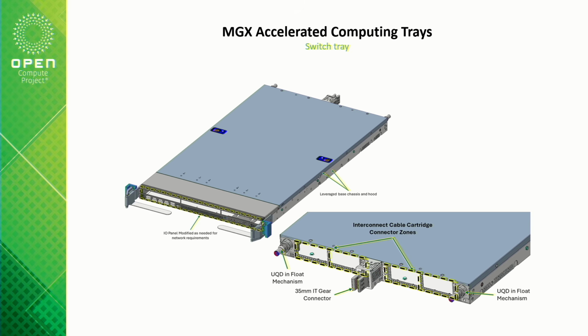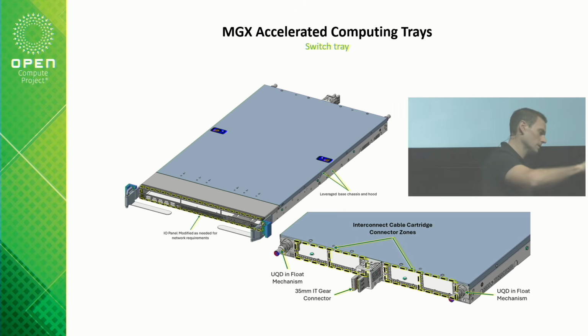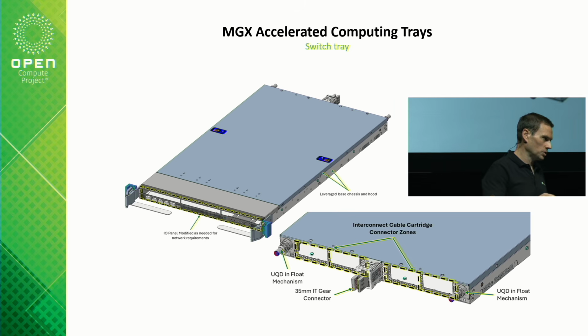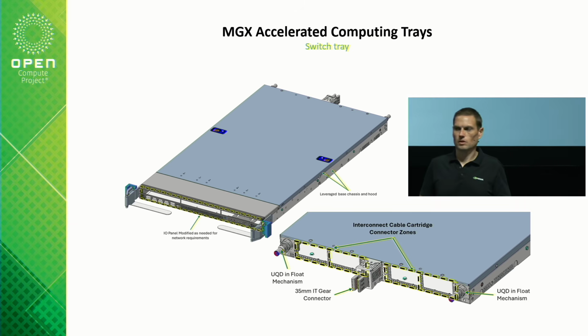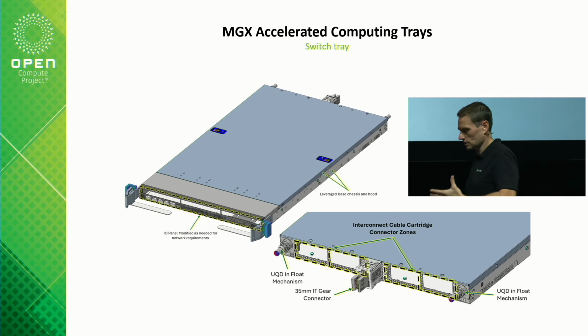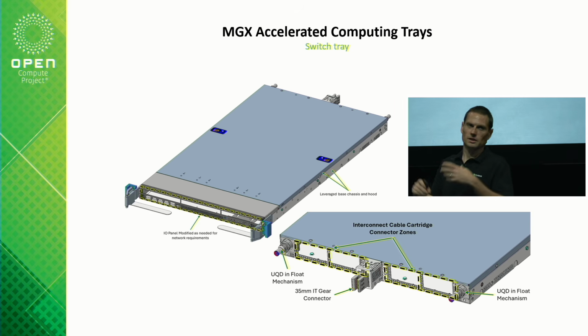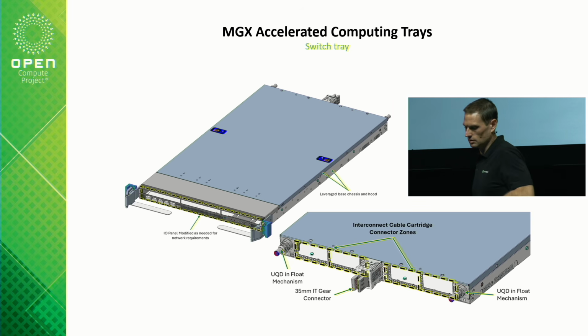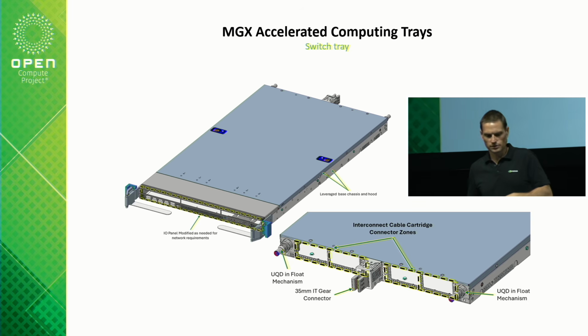You can also notice on the side of the tray some perforations where it says UQD float mechanism, and just above that, more perforations down the side of the tray. That's not something you'd see in a lot of enterprise hardware. The reason is, I haven't talked much about it, but there's also air cooling in the system. We like to talk about liquid cooling, it's very cool, but there's also a fair amount of power that needs to be air cooled.